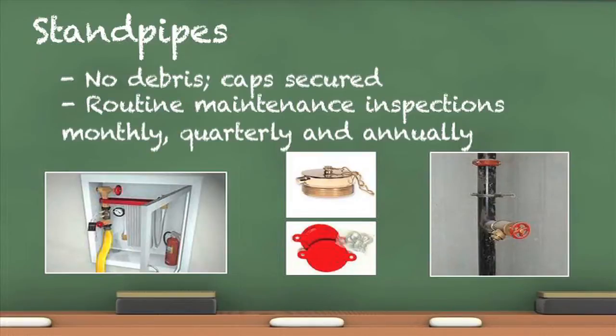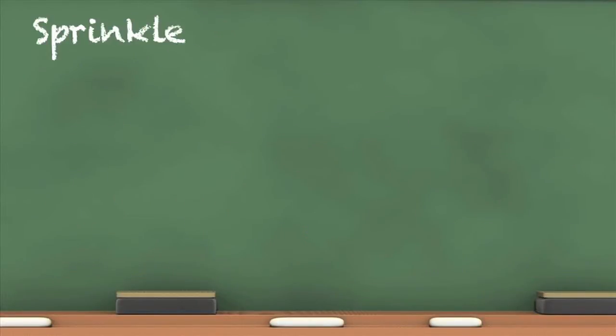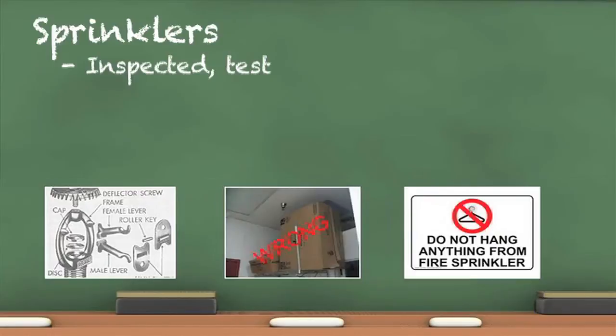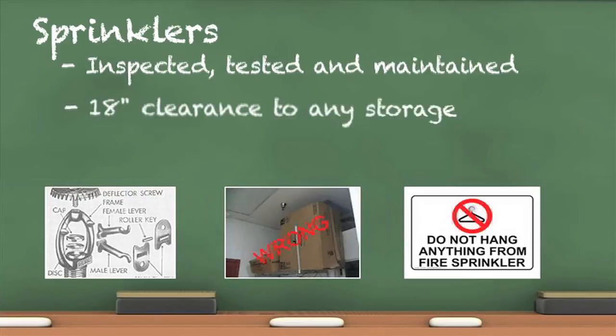Documentation of monthly, quarterly, annual, and 5-year inspection, testing, and maintenance is required. Sprinkler systems are required to be inspected, tested, and maintained monthly, quarterly, annually, and every 5 years. For the sprinkler system to work properly, nothing can be stored above or within 18 inches below the level of the sprinkler head. Nothing can be attached to any sprinkler system component. If the sprinkler system is not functioning, a fire watch is required.